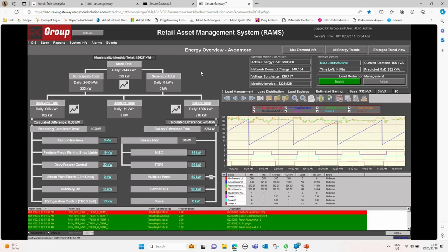The overview gives them a few things. It gives them our max demand info. You can see the max demand going up every half an hour, and we're doing load control with that. We've set the max demand limit to 250 kilowatts.